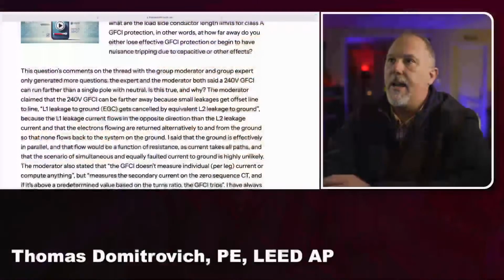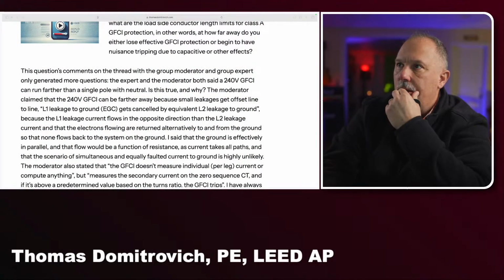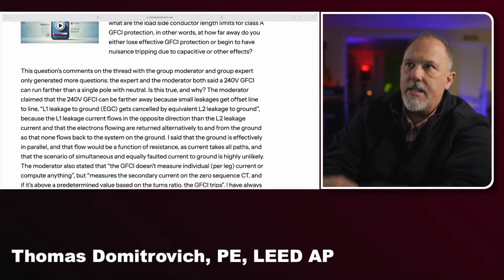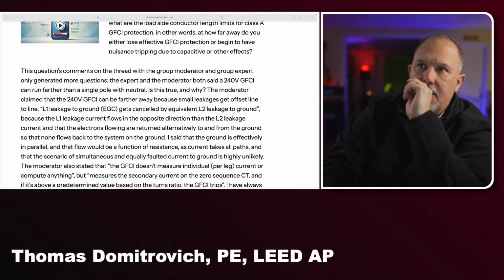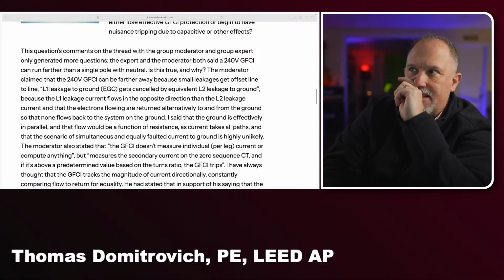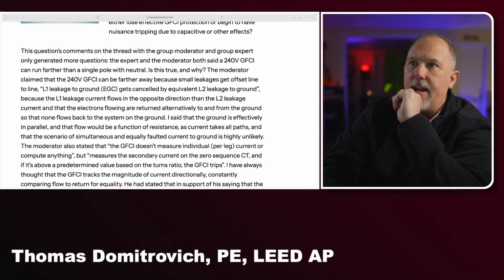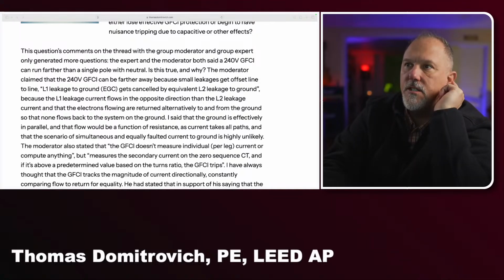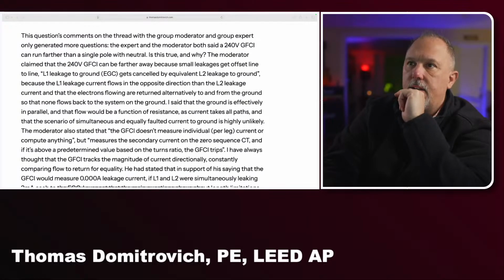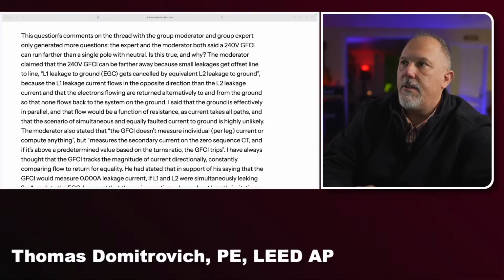The moderator claimed, okay, let me just do this back, L1 leakage canceled by L2 leakage. I don't agree with that. I said that the ground is effectively in parallel and that flow would be a function of resistance, as current takes all paths. You are a smart man. That scenario of simultaneously an equally faulted circuit to ground is highly unlikely.